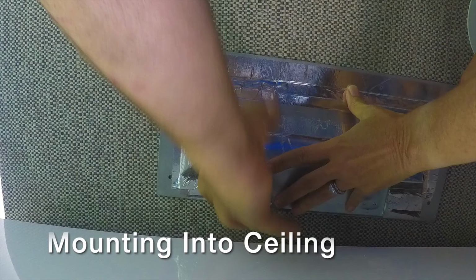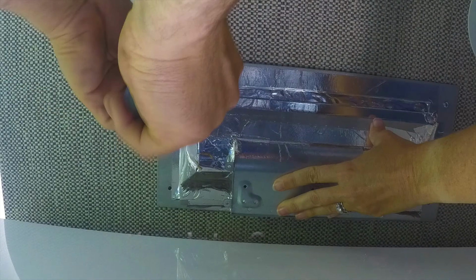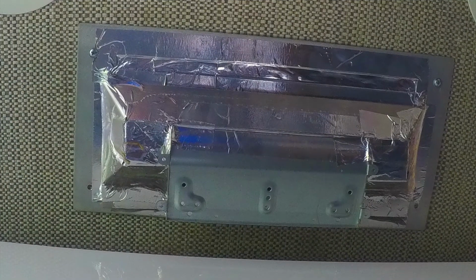Since we're away from the real shop, he can't fabricate a brand new housing. Instead, he made 3 different panels from the old guide vanes to cover most of the opening space, and then to air seal it, he used aluminum foil tape. Once we are back at the shop, a new aluminum cover will be fabricated with this same shape.